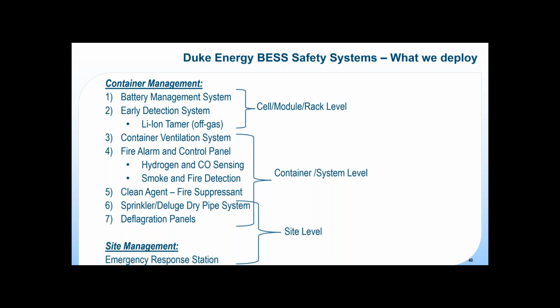Last but not least, if a system gets into complete runaway and we have a buildup of hydrogen gases in the container that somehow wasn't exhausted, we require a full explosion analysis to be done up front on the project so that we maintain a 1 PSI or less pressure wave at the fence line at the site. We want to ensure that should we have an explosion, the pressure is relieved so that we don't injure any public or damage any property outside the fence line.